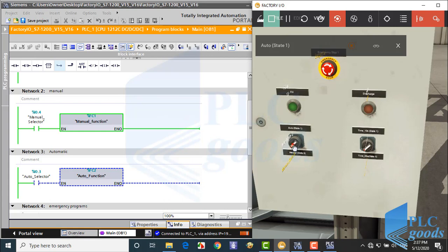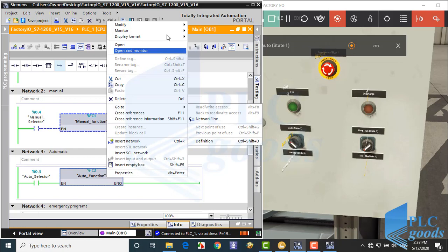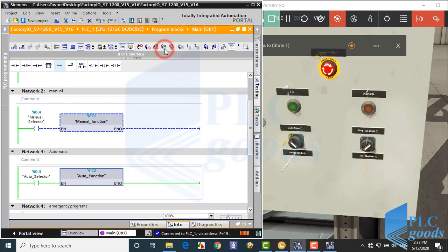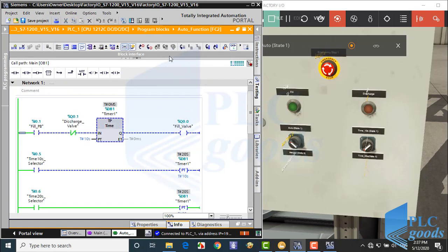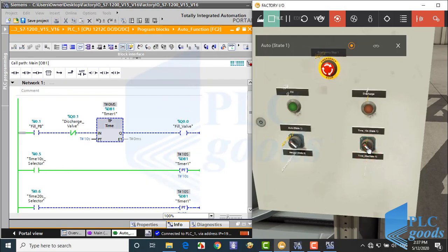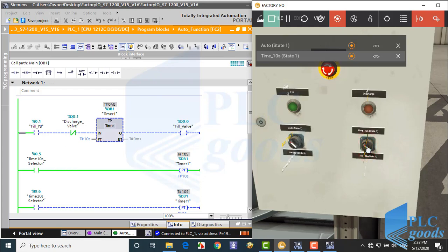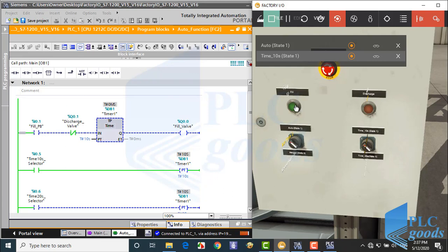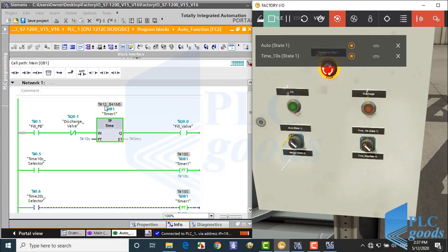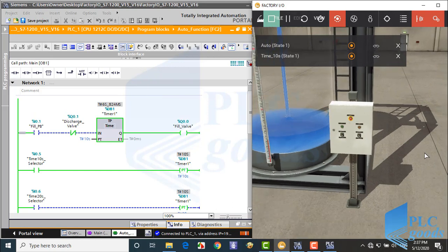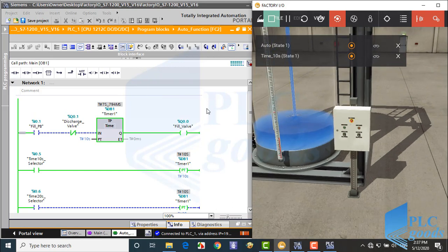Now I select auto mode and then open auto function. In this mode, I can change the preset time with this selector. In auto mode, when I press fill or discharge push button, related valve will be on for the specified time 10 or 20 seconds.